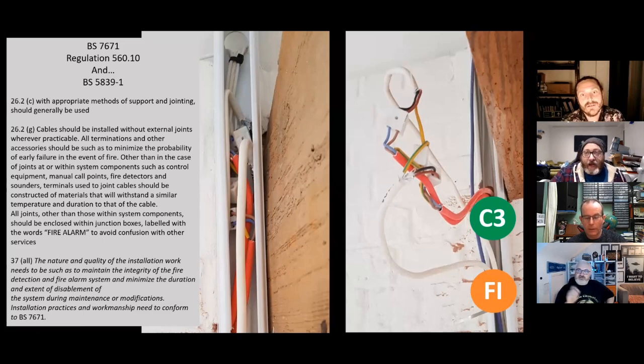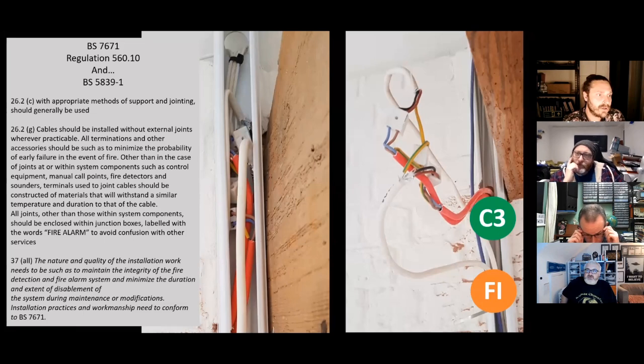Temporary duration. Okay. In these events, I often just see extinguishers being used and that's it, unless there's a marquee that's up for a long period of time. If that's your control measure, if you've done a fire strategy, you will have fire wardens walking with fire extinguishers and enhanced alarm systems and all sorts, whether they're just bells that people can ring, then maybe. But I'd be interested to see the person who'd accept that.